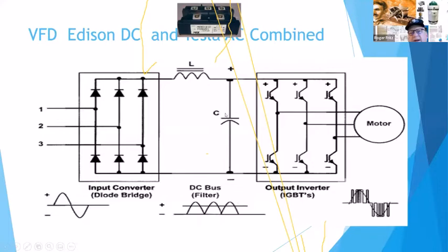DC bus filter power. That's what this is, a line reactor to reduce current surging. And then these are the capacitors that are inside. And all it was doing is basically building us a DC bus supply inside the drive control. Then with transistor outputs, and the original ones I started out with were GTRs, which were giant transistors. Then they went to isolated gates, which are now, but what we're doing is we're building what they call PWM, pulse width modulation, that feeds the motor.